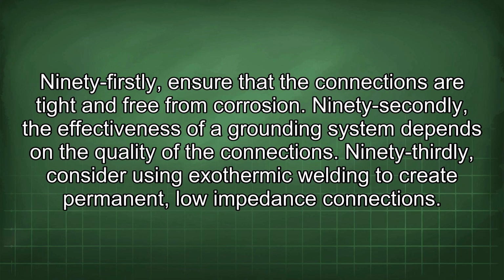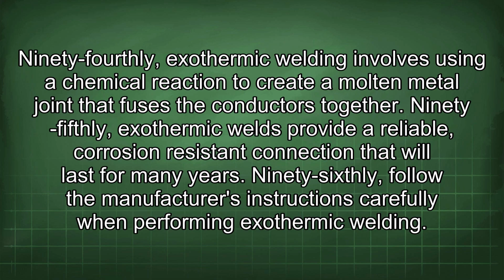92nd, the effectiveness of a grounding system depends on the quality of the connections. 93rd, consider using exothermic welding to create permanent, low-impedance connections. 94th, exothermic welding involves using a chemical reaction to create a molten metal joint that fuses the conductors together. 95th, exothermic welds provide a reliable, corrosion-resistant connection that will last for many years.